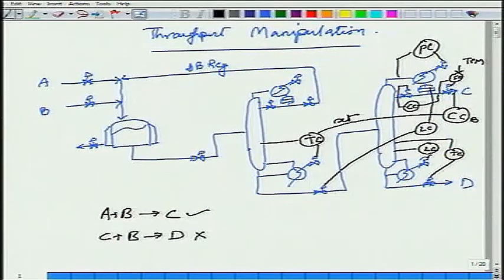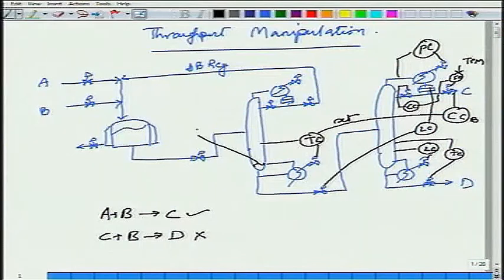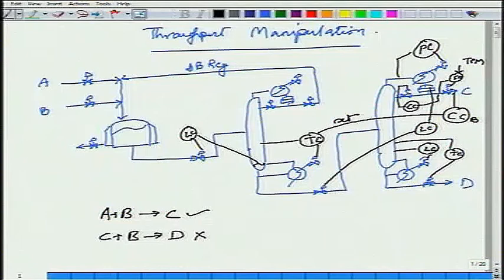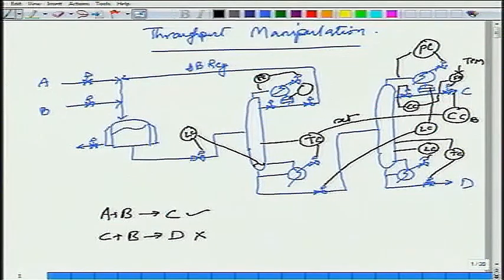How do I control the level in the bottom of the recycle column? My throughput has been set at the product stream, so level control must be in the reverse direction of flow — same as the tanks-in-series example where the TPM is at the product end. Level control is therefore upstream, while pressure control as usual goes the usual way.